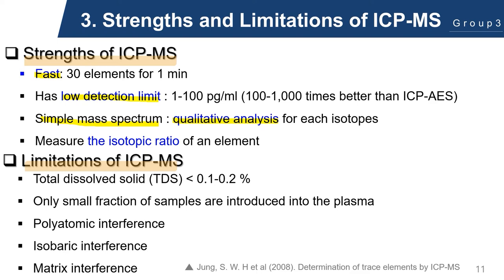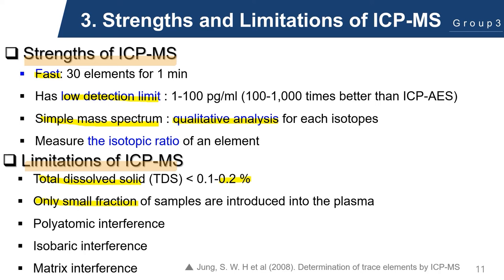Nonetheless, as is the case with any other technique, the ICP-MS also has its trade-offs. One of its most notable limitations is that the total dissolved solid should be limited to less than 0.2%, to ensure that the spray chamber is not clogged by a large influx of aerosols. As a result, only a small fraction of samples can be introduced into the plasma. Then there is the issue of interference. Polyatomic interferences stem from two or more species which combine to give the same atomic mass of a substance that we are interested in.